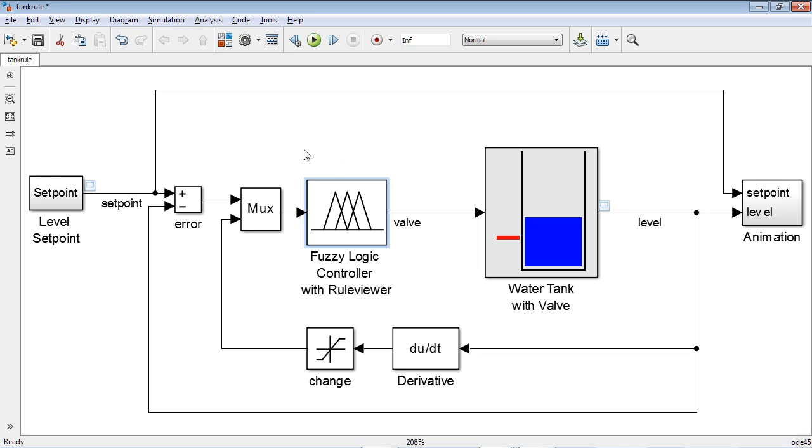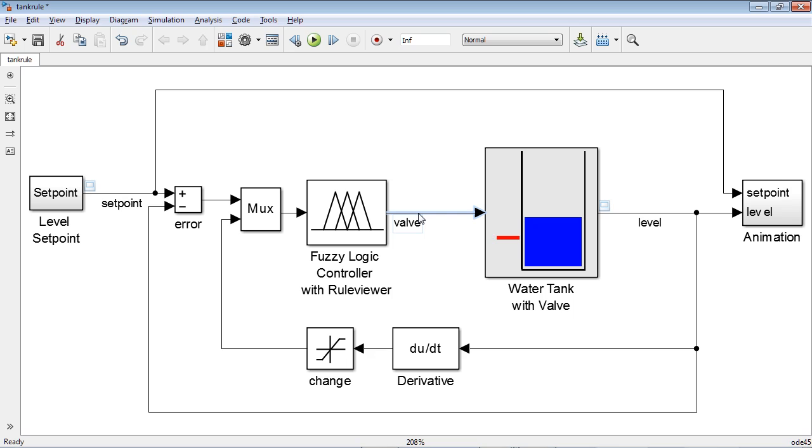As you can see, the Fuzzy Logic controller has two inputs. The first one is water level error, which is the difference between the setpoint and measured water level, and the second input is change of rate of the water level. The output of the controller is the calculated valve position for controlling the tank inflow rate.